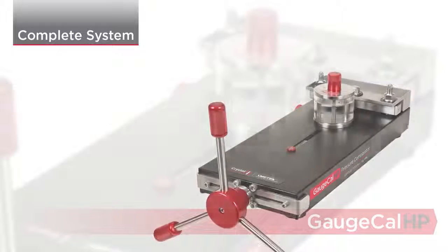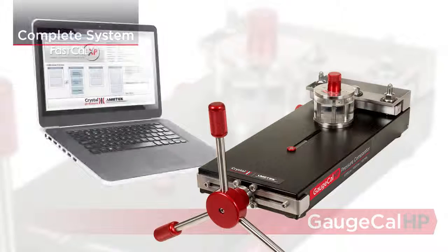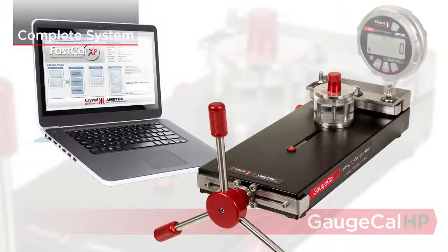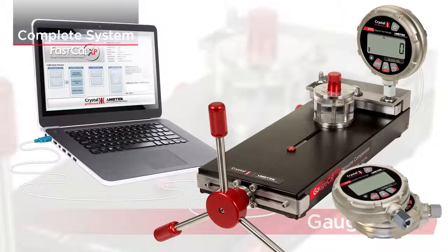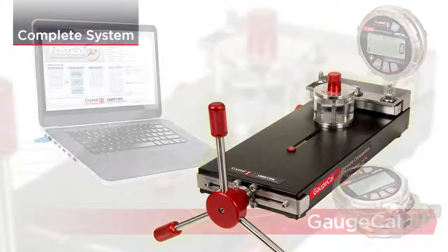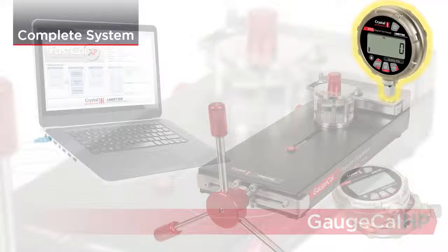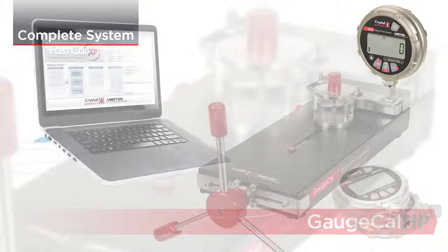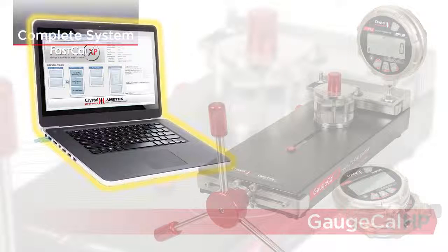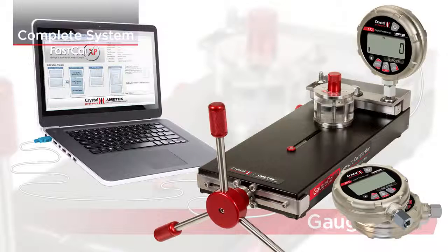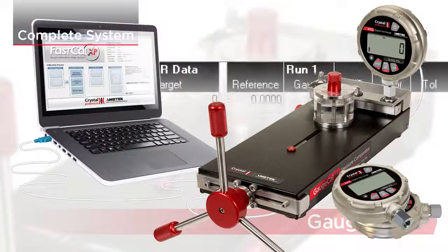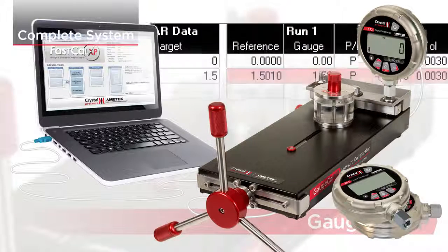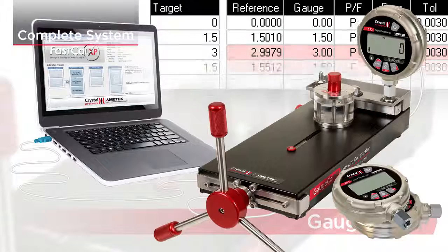Combine the GaugeCalHP with our FastCal XP software and XP2i pressure gauges to create a complete calibration system. The GaugeCalHP provides the pressure, the XP2i accurately reads the pressure, and FastCal XP collects data directly from the XP2i and produces a calibration certificate. Eliminate typing, reduce calculation errors, and complete a 10-point up and down calibration in less than 3 minutes.